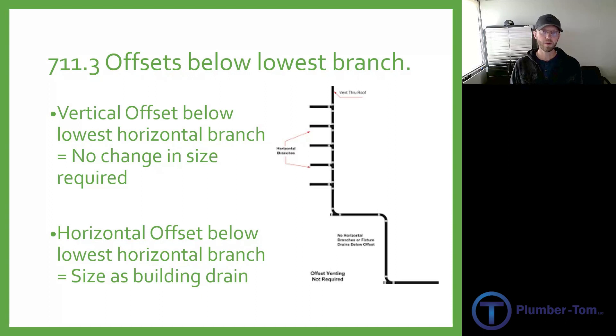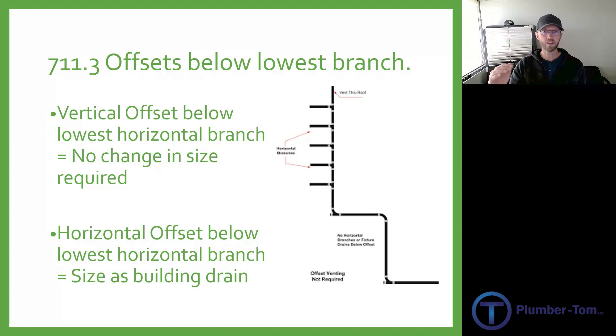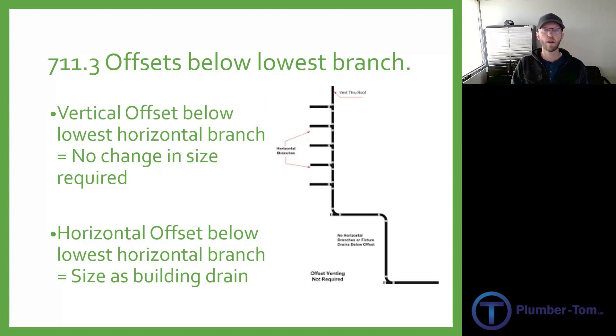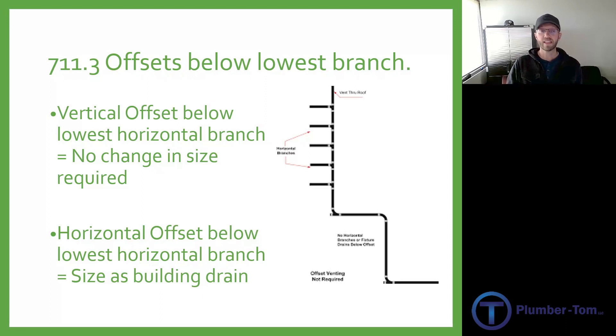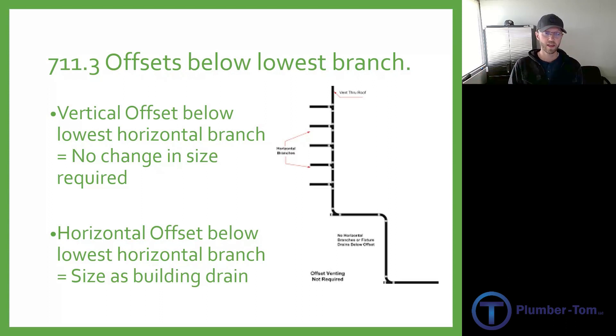7-11.3 talks about offsets below the lowest branch. Say we have a vertical stack with horizontal branches coming into it, but at the very bottom it offsets and there are no other connections below that. For a vertical offset, we will not have to change the size. However, in the case of a horizontal offset below that lowest horizontal branch, it would still need to be sized as a building drain once that pipe turns horizontal.